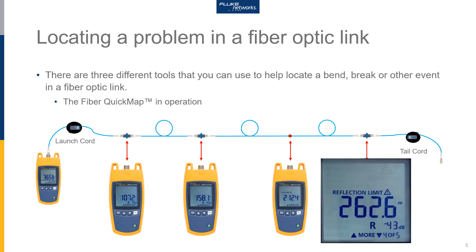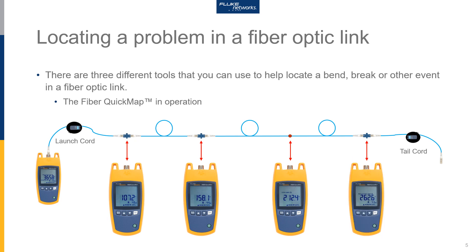Finally, at 263 meters, I have the fourth event. Because I've got a tail cord on the end, I know this is the last connector on the link I am measuring. I've got a reflection limit alarm showing here — it's a reflective event, a connector. But it is at minus 43 dB. I set my limit at minus 45 plus or minus 1 dB, so this is indicating that at 263 meters I have a dirty connector.